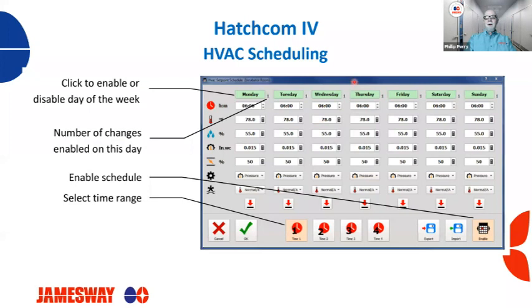We wouldn't want to be doing any scheduling on our incubator rooms or our hatch rooms, although some multi-stage hatcheries have used this because they like to cool their multi-stage machines down to 95 or 94 degrees to hold chicks. Once the hatch is completed, they'll program a schedule so that every Wednesday, or whenever the hatch is starting to peak and they're starting to drop their cooling down, they can do that for that room. Again, if it's connected to Hatchcom through our Guardian system, it's a very, very good feature for energy savings and also, depending on how you use it, to help in chick quality.